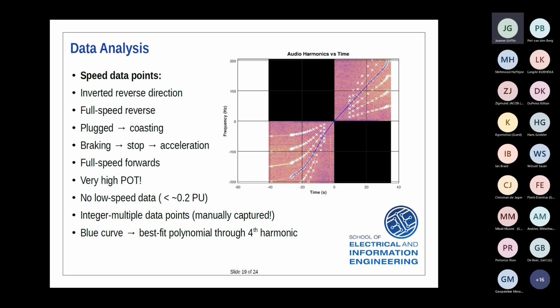Just to show you once again: the machine is running full speed backwards. We disconnect the phases, reverse it, and re-energize it. In that time, the machine is coasting, so this straight line here. The machine coasts while we're plugging it, and then when we re-energize it, it starts to brake. It decelerates very quickly to standstill momentarily, then accelerates in the forwards direction to free running speed, and runs almost full speed to full speed forwards.